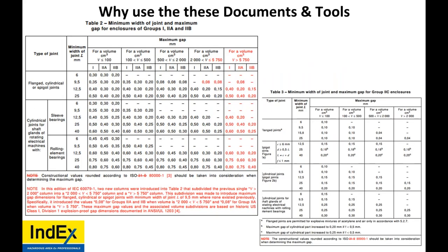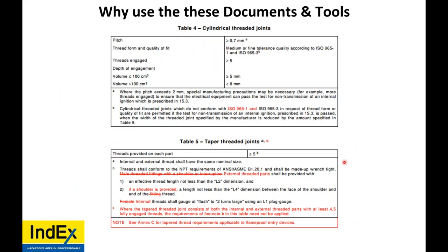Now, going by opinion doesn't mean anything. With those tools, you can at least verify, with use of the certificate, IOMs, and standard, with a legitimate tool that has been calibrated. So, cylindrical and tapered threads. There are other considerations. Be aware of this. Inspectors only work to 60079-14 and 17. Torque settings are generally on the cert or IOM. Correct, but 14 is for inspection.